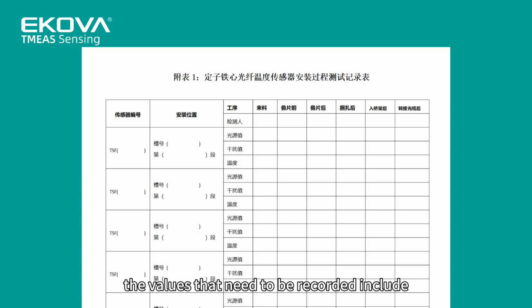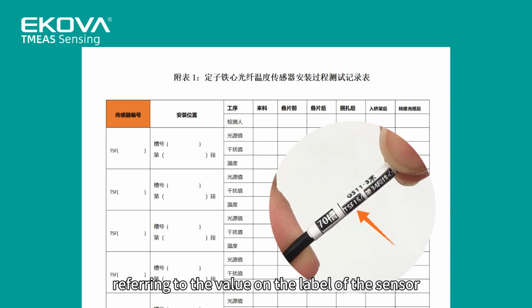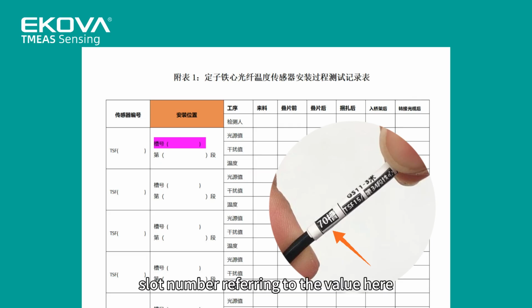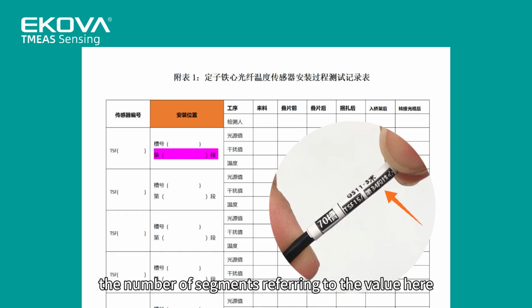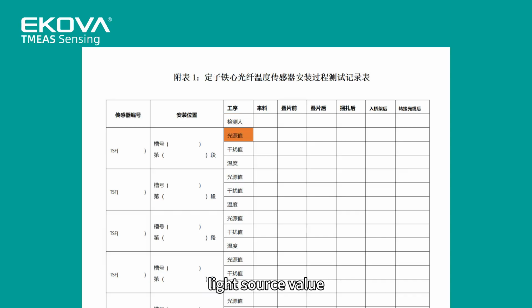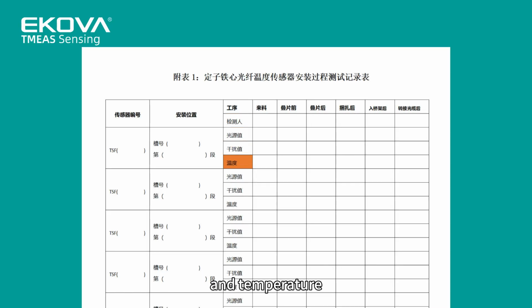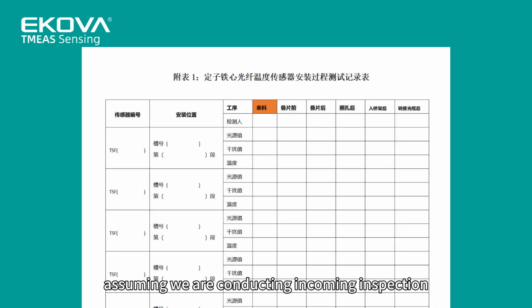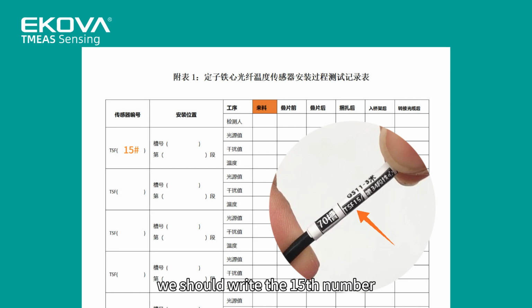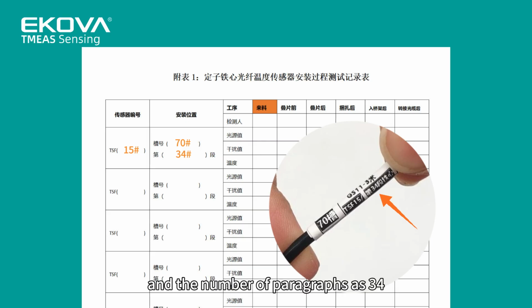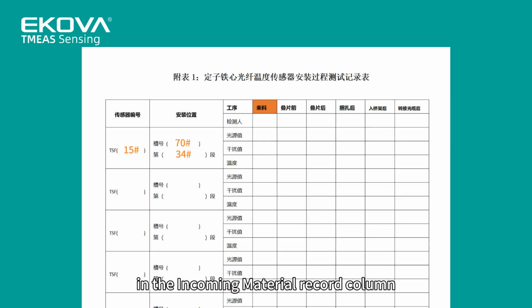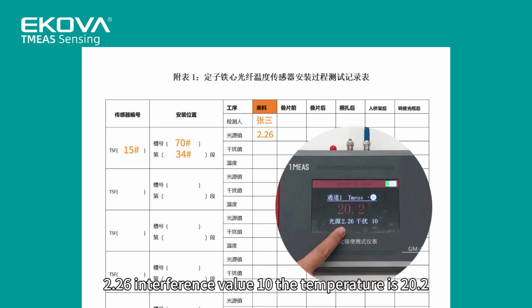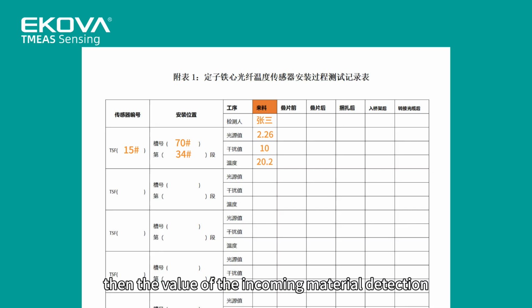The values that need to be recorded include the sensor number, referring to the value on the label of the sensor, the installation position slot number, referring to the value here, the number of segments, referring to the value here, and then the detection person, light source value, interference value, and temperature. Write the process on site in the same column. Assuming we are conducting incoming inspection, we should write the 15th number in the sensor number column. Write the installation position slot number as 70 slots, and the number of segments is 34. In the incoming material record column, the inspector writes, for example, Shangsan, light source value just measured, 2.26, interference value, 10. The temperature is 20.2, then the value of the incoming material detection process is recorded.